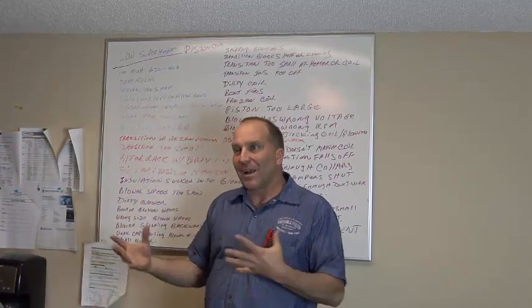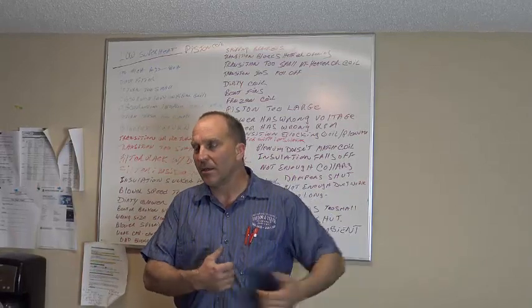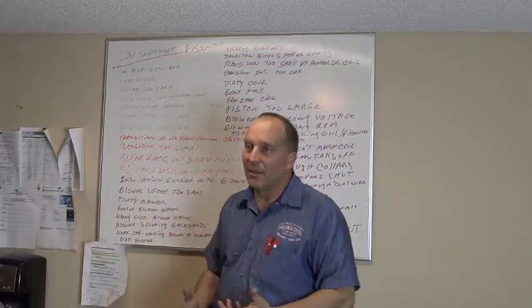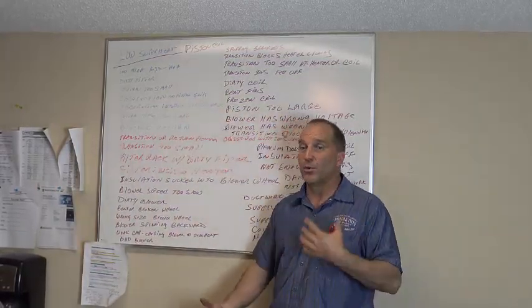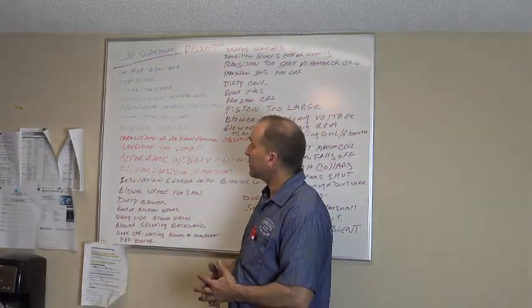That gives you a really high static pressure in your return. That tells you return air is blocked up. Okay, so we're going to do a class on magnehelic gauges and incline manometers to put this to real life as well. Okay, let's continue this down.